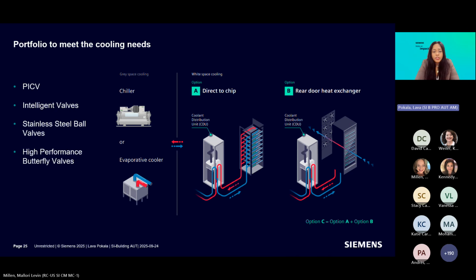Our portfolio is constantly evolving to support the latest cooling innovations, like the liquid cooling infrastructure we saw earlier. Siemens pressure independent control valves and intelligent valves directly support this liquid cooling technology, providing precision liquid flow control. Our portfolio is constantly being updated to meet market needs with stainless steel valves that are corrosion resistant and can be used in direct-to-chip cooling distribution units or rear door heat exchangers.